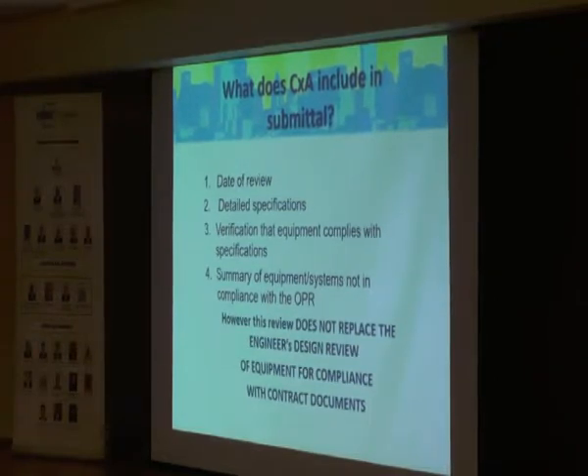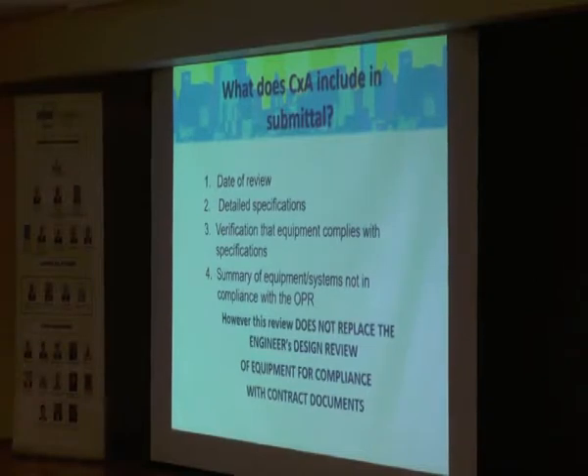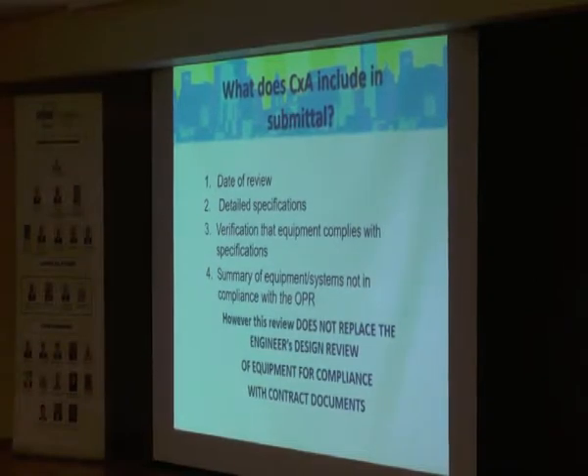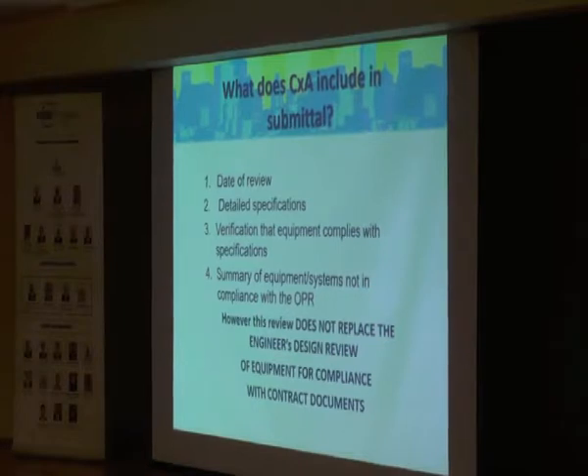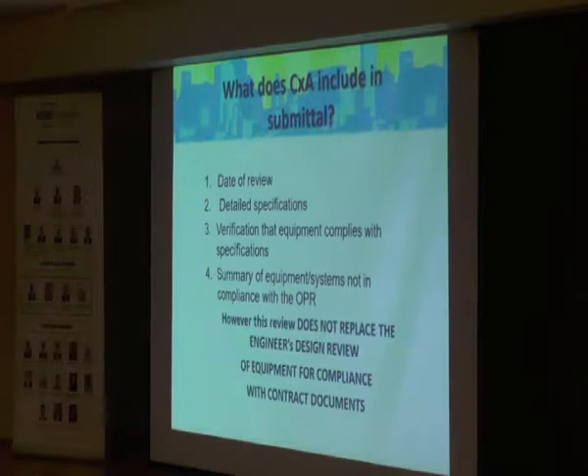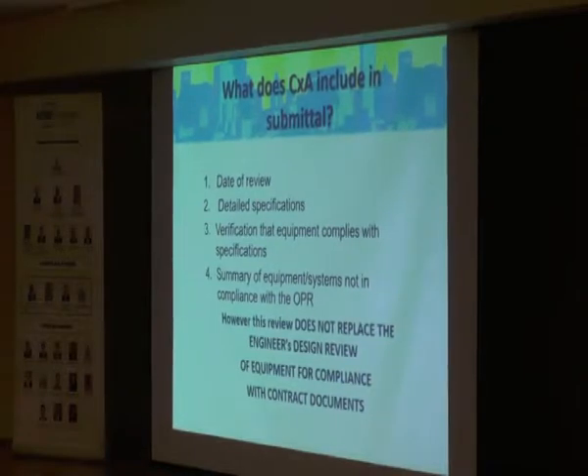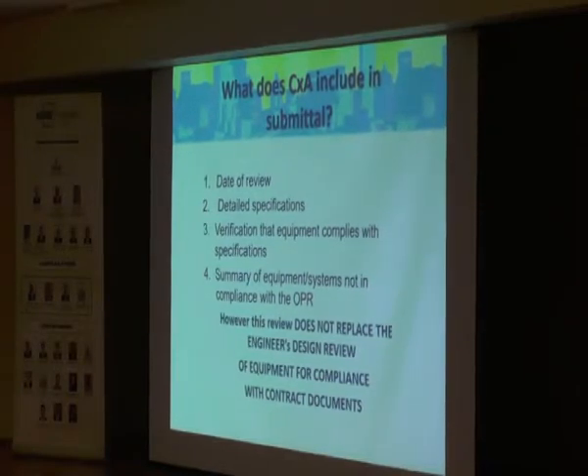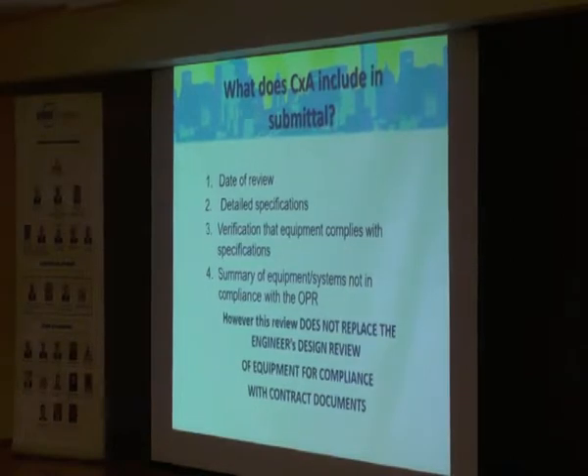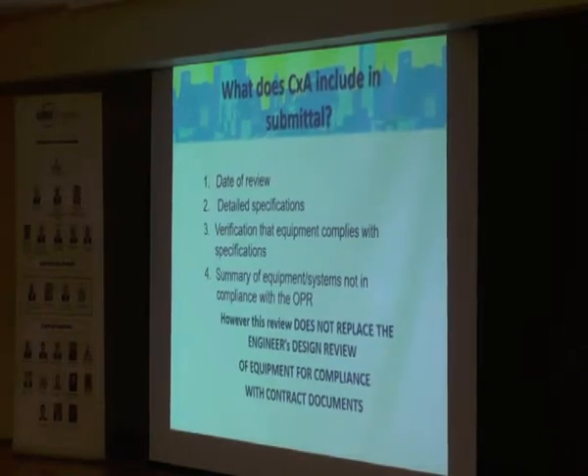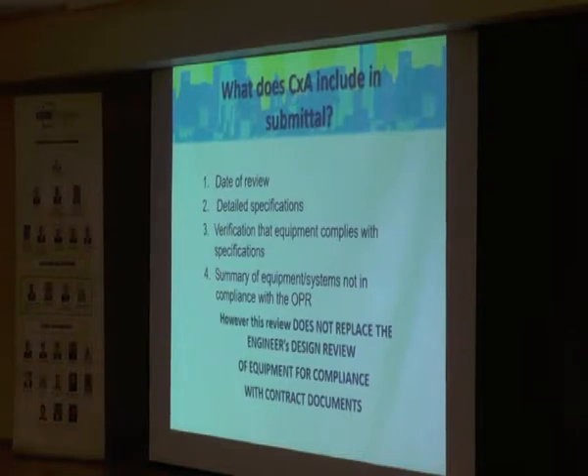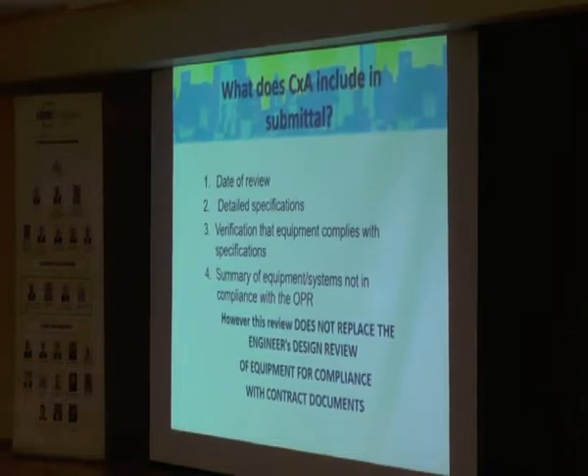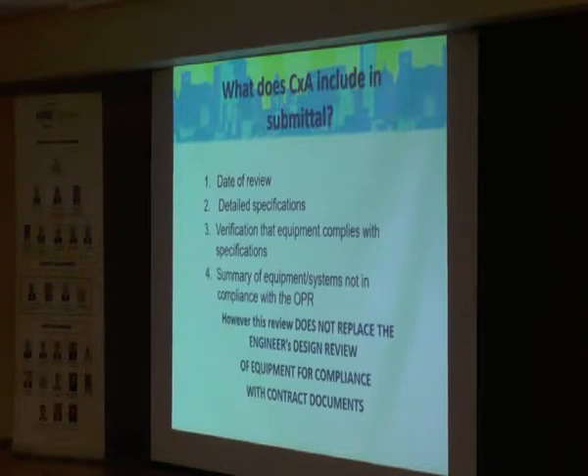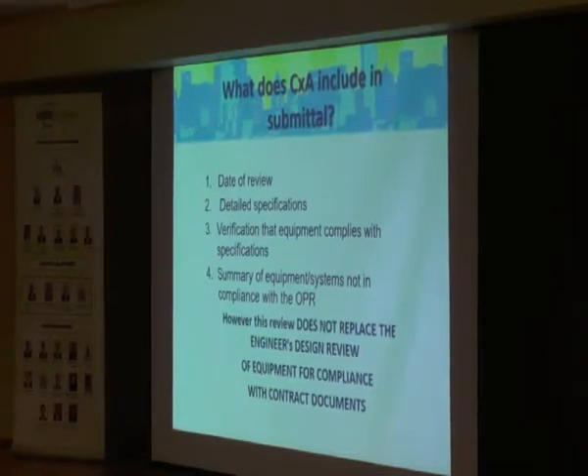It required crane operators twice on two different nights, because all this work had to be done after midnight. Secondly, we found that the structural system was not adequate to handle the two cooling towers. This is where, as a civil engineer, I had some input to the whole procedure. As it turned out, it was not a constructible job because it was not accessible enough to run and maintain those towers properly—there just wasn't enough room.